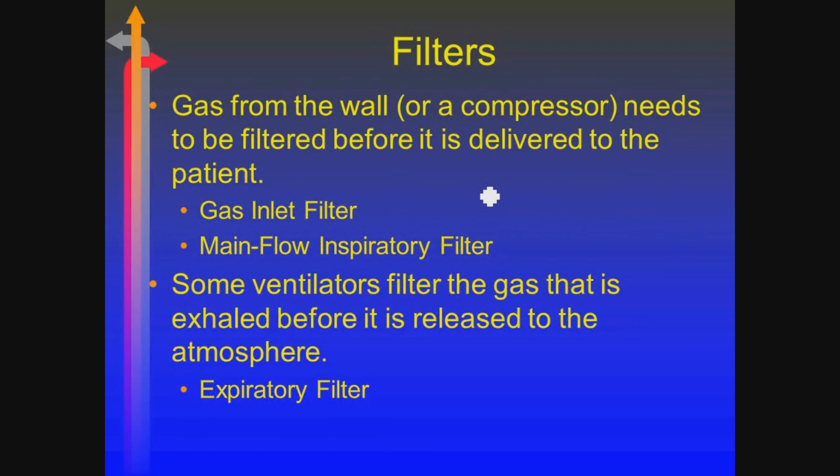We also then have a main flow inspiratory filter. Most places utilize, some places don't, but you're basically using a high efficiency filter to filter it once again. And there are some ventilators that have filtering of the exhaled gas also, which when you think about it probably is the smartest thing. If your patient has any kind of respiratory disease, you don't want to have that just being dumped into the atmosphere without going through a filter of some kind.